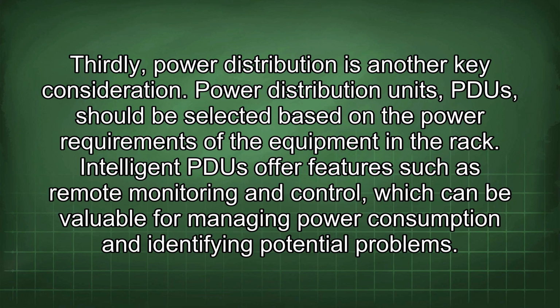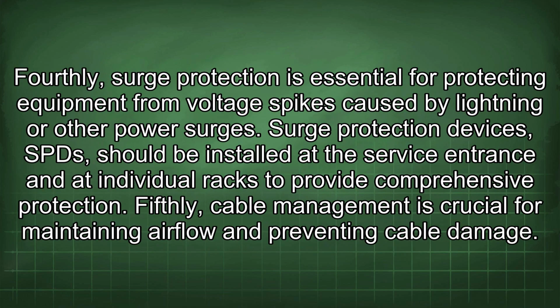Power distribution units, PDUs, should be selected based on the power requirements of the equipment in the rack. Intelligent PDUs offer features such as remote monitoring and control, which can be valuable for managing power consumption and identifying potential problems. Fourthly, surge protection is essential for protecting equipment from voltage spikes caused by lightning or other power surges. Surge protection devices, SPDs, should be installed at the service entrance and at individual racks to provide comprehensive protection.